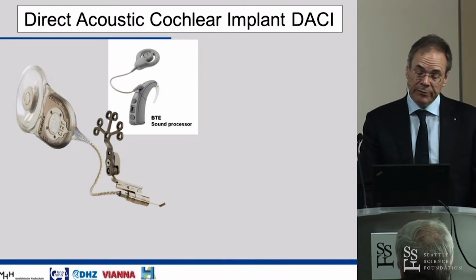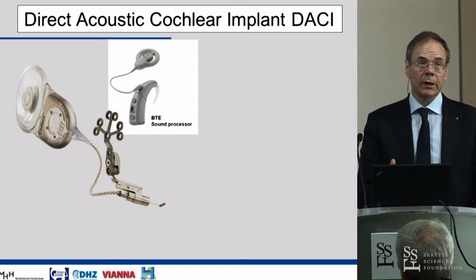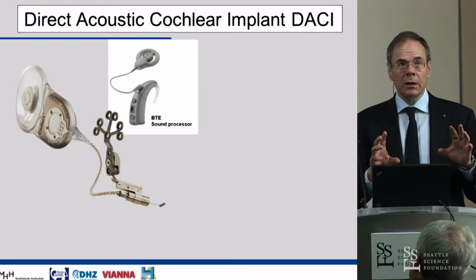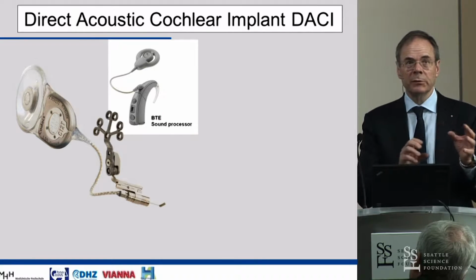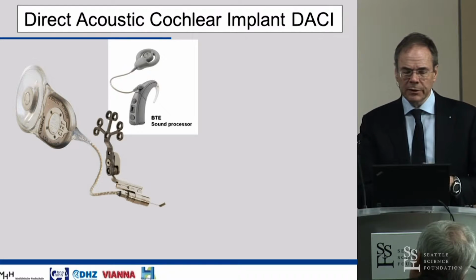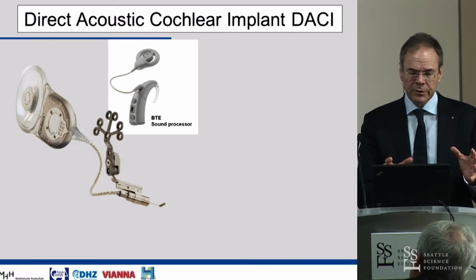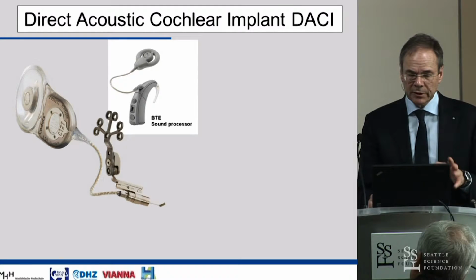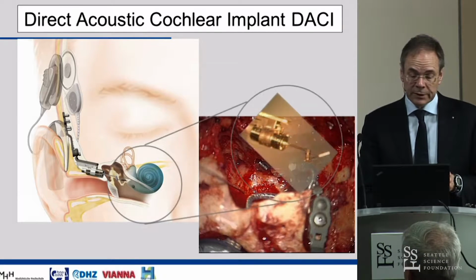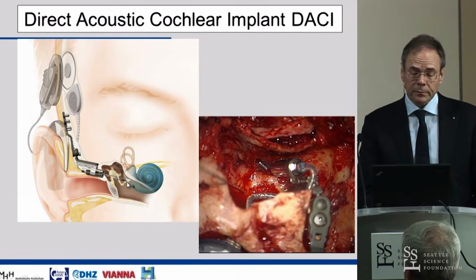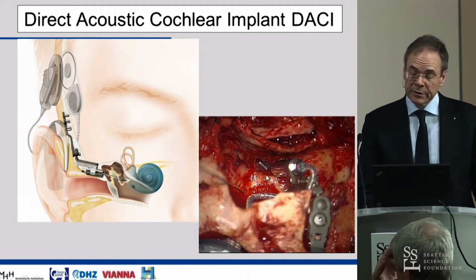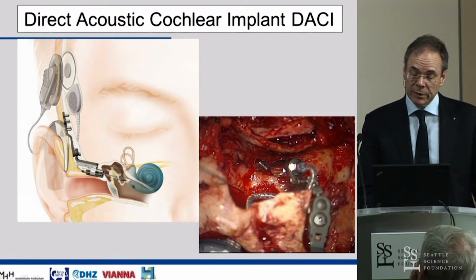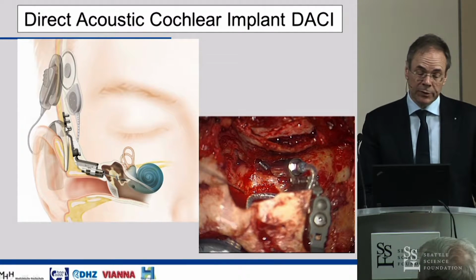Now, one step further is going directly into the inner ear. So why should you stay outside and have all these coupling issues? How to fix these transducers on some of the ossicles might be difficult, as you know from middle ear surgery. Therefore the concept was to go directly into the inner ear, and that's done with this direct acoustic cochlear implant. What it does is basically you use a stapes piston that goes through the footplate, for instance in cases of otosclerosis, and then this piston is attached to this transducer. It's also mounted at the rim of the mastoid, as we have seen before, and this transducer has an artificial incus, which you can see here.